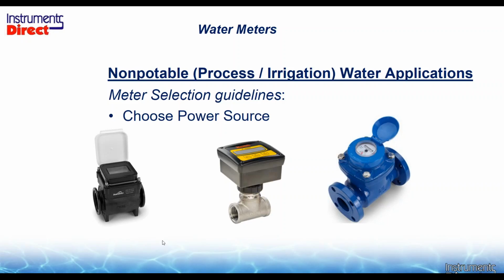But I would like to have a magnetic flow meter there because it's more accurate and has no moving parts. What can you do for me? In this case there, you have a battery-powered magnetic flow meter, and this is one of many variations. So this is a budget-priced plastic magnetic flow meter, and it goes up. You can spend more money and get the traditional flanged metal magnetic flow meter there that runs off a battery as well.